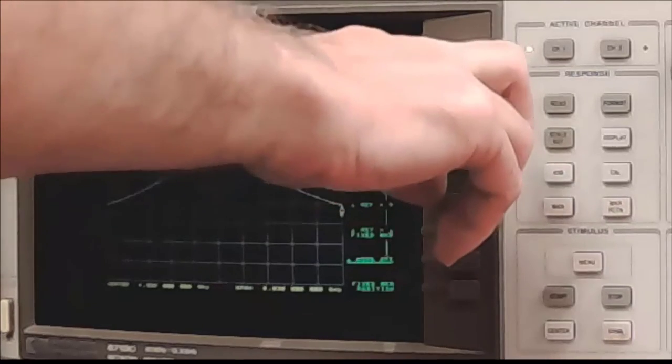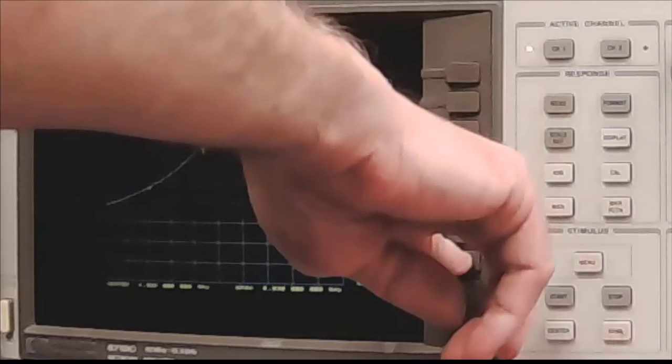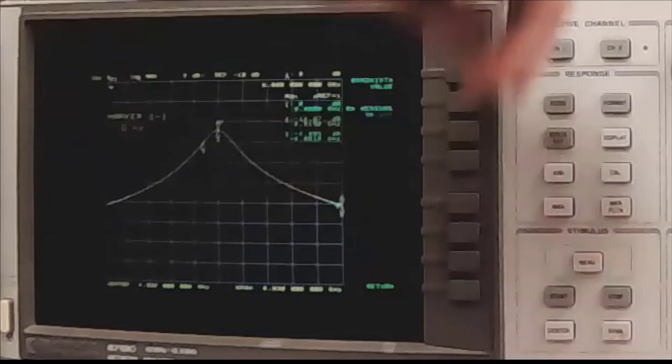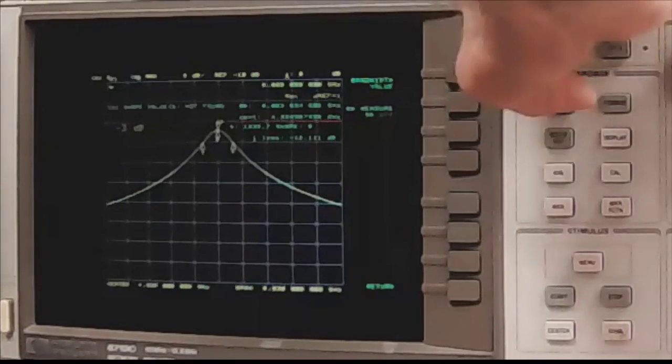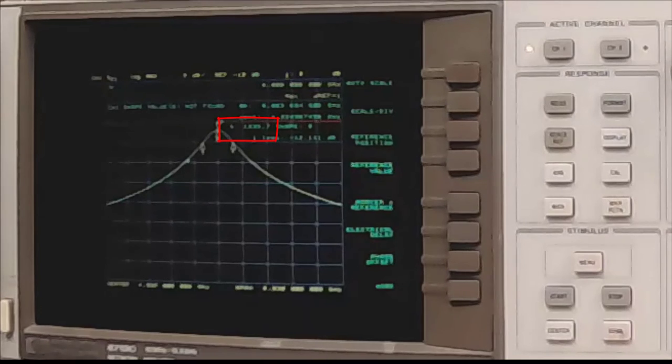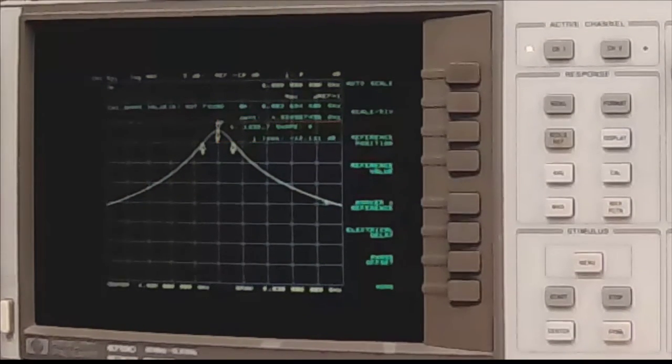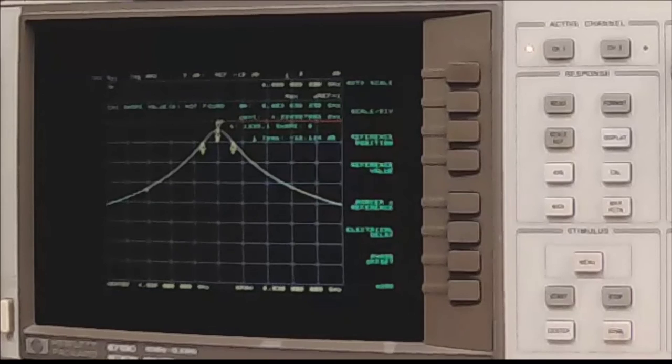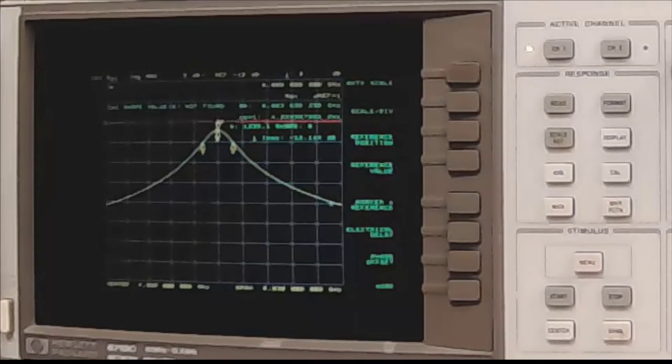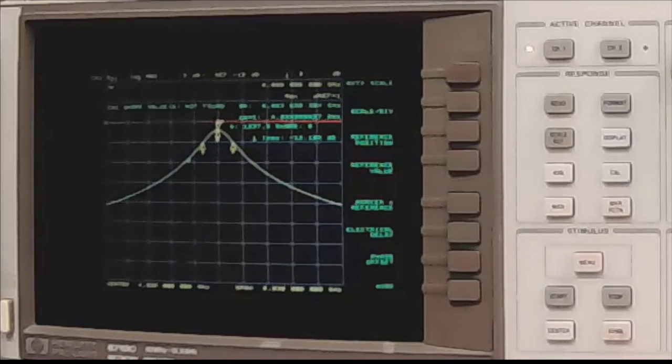Delta Mode, set the reference to marker one. Marker function, tracking is on. Peak search is set to max. Bandwidth menu, and bandwidth is turned on. Make sure the width value is set to minus three decibels. We have a loaded Q of 1,335. It's a little bit different from the last sweep, but that could be because I unscrewed the cavity in order to detune the resonator. The detuning and retuning of the cavity can make the Q a little bit different.